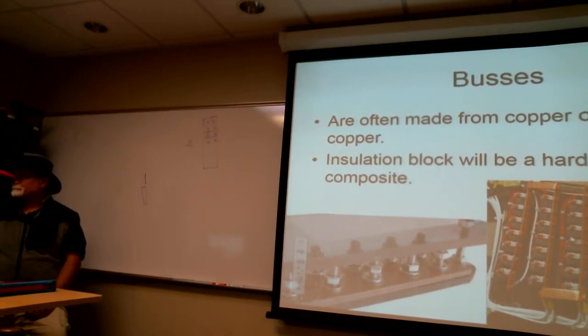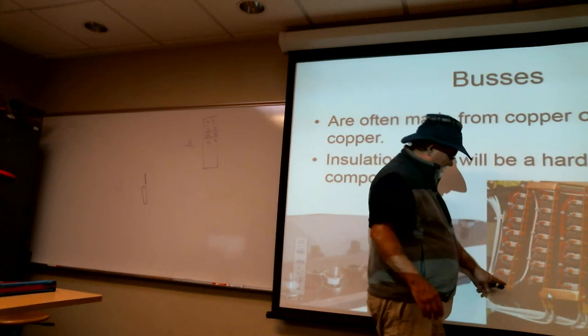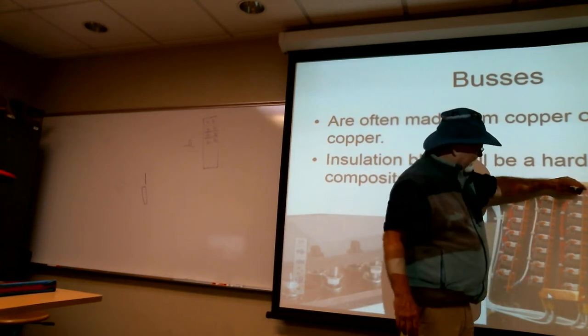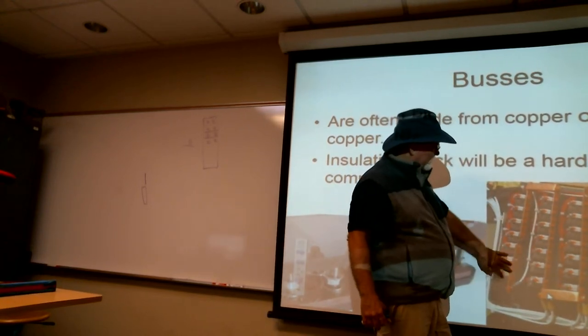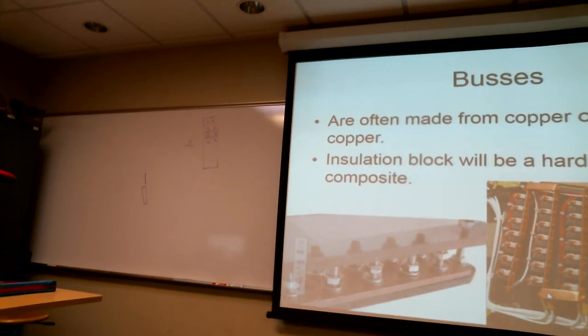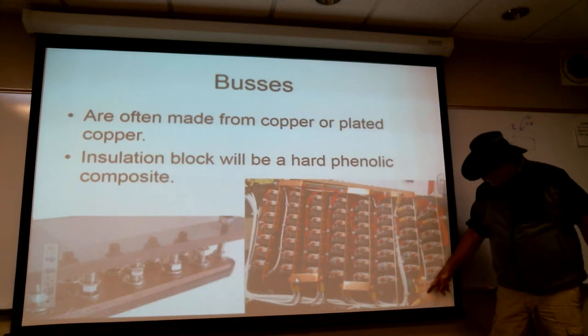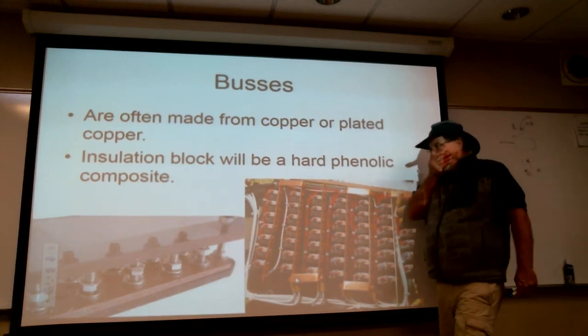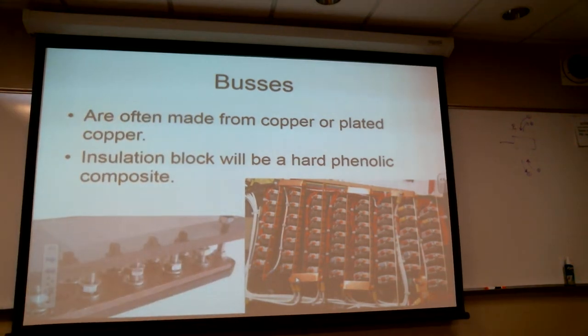This one here looks like a homemade bus — insulator plate, copper bus, looks like a cover guard. You can see the copper bar interconnects all the way across here — all of that is one bus. This is a separate bus, this portion here is one bus, and this portion here looks to be another bus as well. In this assembly they've got four or five different bus assemblies.